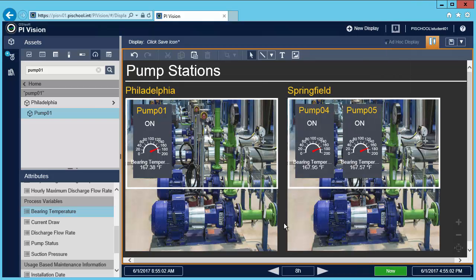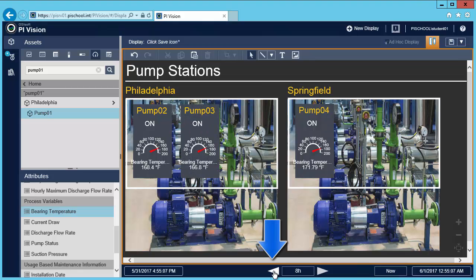I'll hit refresh and do the same for this second collection. Now the collections will automatically update to show me only the pumps whose bearing temperature requires my immediate attention. So if I go back in time they're going to update. In the future, if new assets get added to my AF hierarchy, I don't have to worry about adding them to my collection — PI Vision will pick up the new assets automatically as long as their data falls within my criteria. Let me save the display.